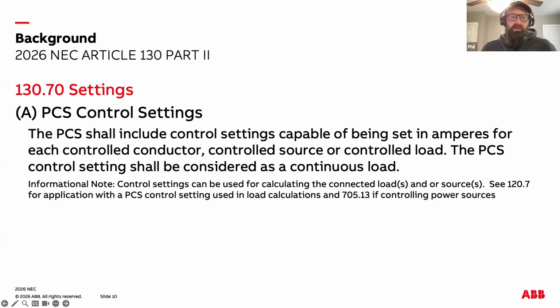Another key provision in Part 2 of Article 130 allows PCS control settings to be used when calculating connected loads or sources. The requirement means that a PCS must be able to set a specific ampere limit for every conductor, source, or load it controls, and that this limit is treated as a continuous load for code calculation purposes. In simpler terms, the PCS must let you program an exact current limit in amps for each controlled circuit, and whatever limit you set is assumed to be operating continuously when performing NEC load calculations. This ensures the PCS can reliably cap current on each protected path, and that the electrical system is sized as if that limit is always present. We'll look at some examples of this later.